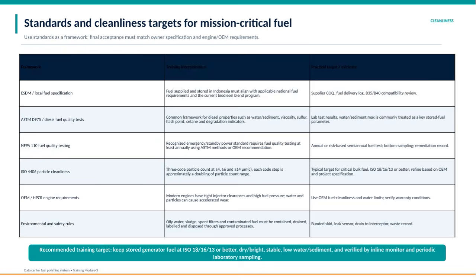Finally, environmental and safety regulations mandate that any oily water, sludge, spent filters, or contaminated fuel must be properly contained, drained, labeled, and disposed of according to approved procedures. Proper infrastructure like bund skids and leak sensors help manage these risks effectively. As a recommended training target, stored generator fuel should maintain a cleanliness level of ISO 18/16/13 or better, be dry and bright, stable, low in water and sediment, and verified through inline monitoring combined with periodic laboratory sampling. This comprehensive approach ensures that mission-critical fuels meet the highest standards for performance, safety, and environmental compliance.